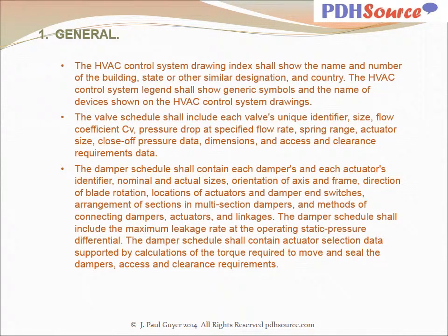The HVAC control system drawing index shall show the name and number of the building, state, or other similar designation and country. The HVAC control system legend shall show generic symbols in the name of devices shown on the HVAC control system drawings. The valve schedule shall include each valve's unique identifier, size, flow coefficient C sub V, pressure drop at specified flow rate, spring range, actuator size, close-off pressure data, dimensions, and access and clearance requirements data.